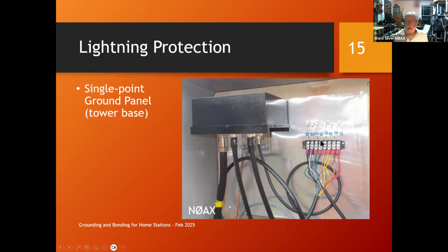And then each one of these wires has a gas discharge tube, cost about $1. You buy them in a box of 100 from Mouser Electronics. You get the 75-volt ones, which are the small ones, connected just to a sheet metal screw on the aluminum flashing. Just get a drill, poke it in there, put in the screw, use the leads of the conductor, and you're good to go. So that's way cheaper than buying special hardware.